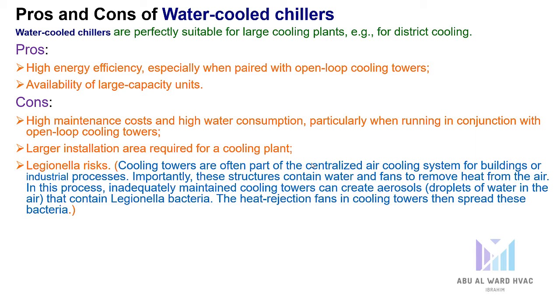Legionella risk. This is a type of bacteria affecting the cooling towers because cooling towers are often part of the centralized air cooling system for buildings or industrial processes. Importantly, these structures contain water and fans to remove heat from the air. In this process, inadequately maintained cooling towers can create aerosols, droplets of water in the air that contain Legionella bacteria. The heat rejection fans in cooling towers then spread these bacteria.